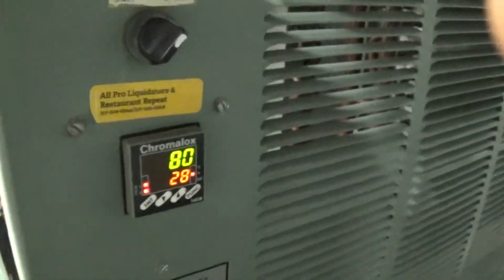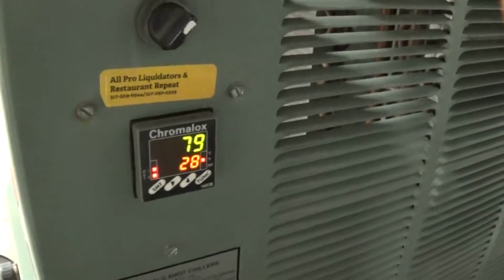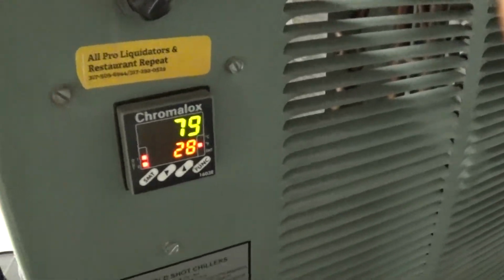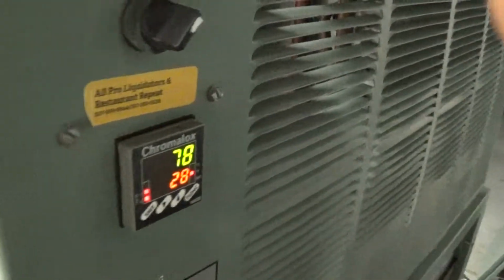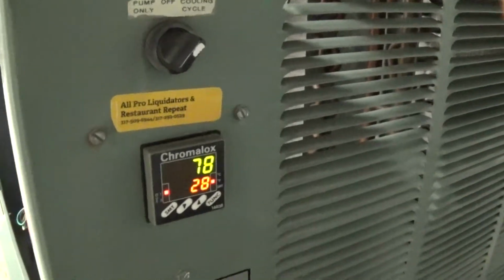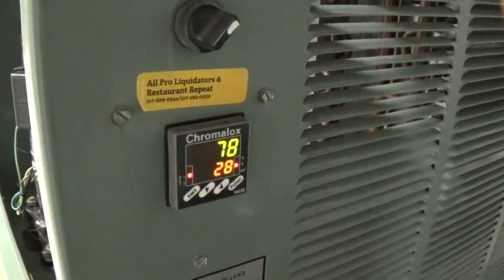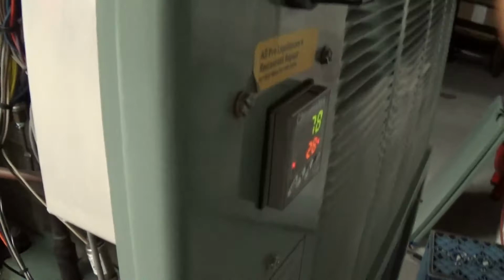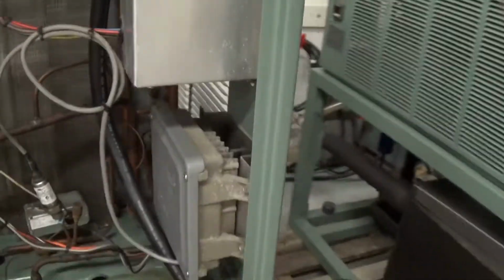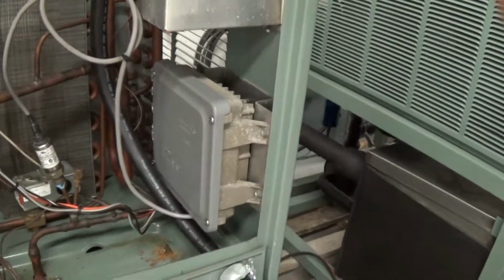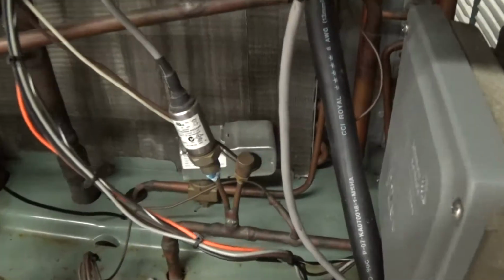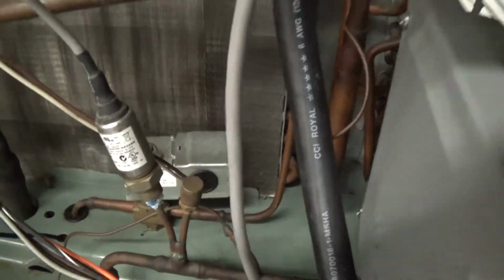So we're chilling right now, and what you just heard is the fan kick on. So this unit has, for whether you need it or not, for colder running environments, it has a combination of fan switching and fan speed control in conjunction with this hot gas bypass valve.